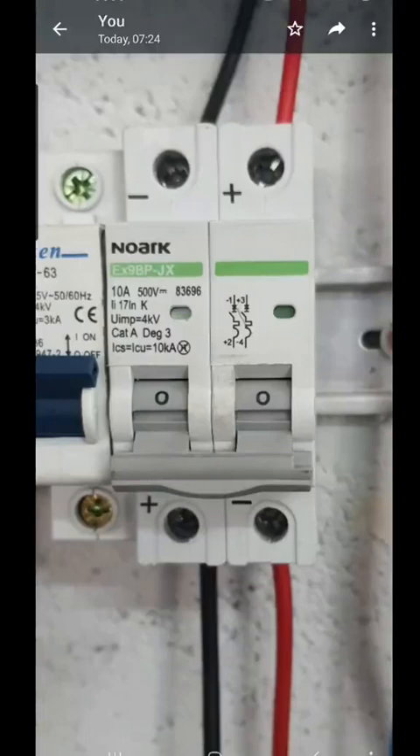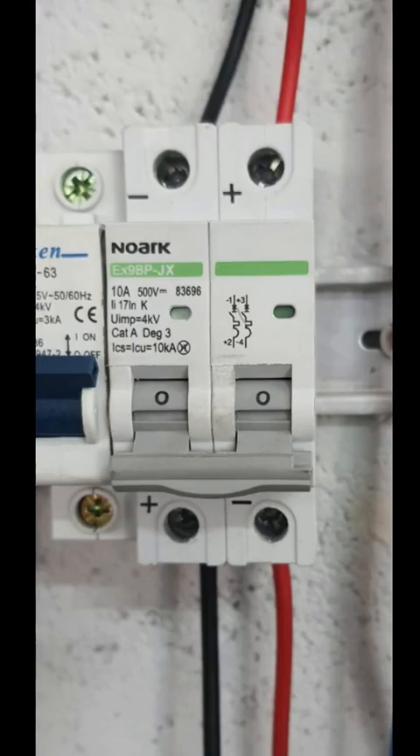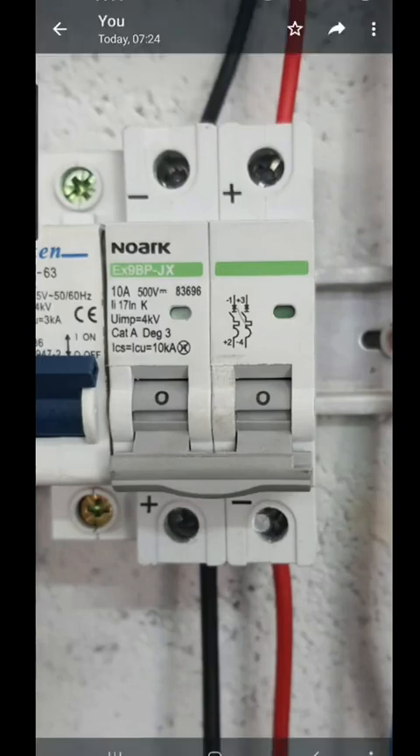What is wrong? Can you spot the fault here? And it's not a misprint, first of all. This is very dangerous. I have contacted Noark themselves to find out if I'm mistaken or who's mistaken here, because there's very confusing. If you look there, it's negative, positive. Here you get positive, negative.